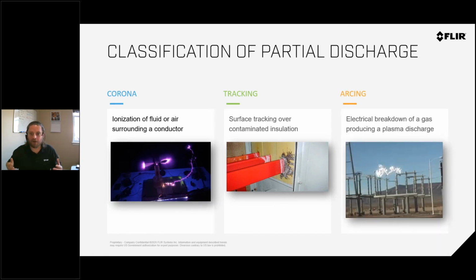And then arcing. Arcing is electrical breakdown of a gas producing a plasma discharge. And this can be very dangerous. This is probably the most dangerous of all 3 because a lot of these are in your substations, and a lot of these connectors are going to have porcelain around them. When you have this arcing, and if it does turn into an explosion, you will have porcelain flying everywhere, and that debris, shrapnel, can be destructive to other surrounding equipment. And once it's flying in the air, it could be very harmful to people on the ground that might be around it. So arcing is definitely what we don't want to see happen, and probably the most dangerous of all three.